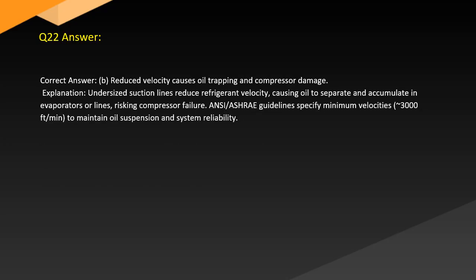Answer. Correct answer: B. Reduced velocity causes oil trapping and compressor damage. Explanation. Undersized suction lines reduce refrigerant velocity, causing oil to separate and accumulate in evaporators or lines, risking compressor failure. ANSI/ASHRAE guidelines specify minimum velocities, 3,000 feet per minute, to maintain oil suspension and system reliability.